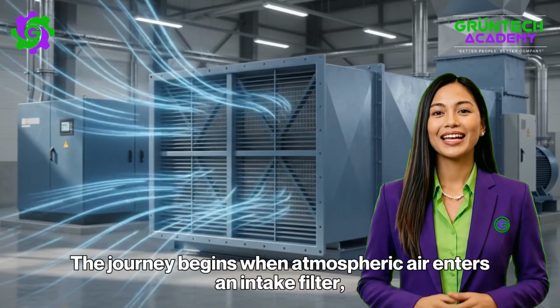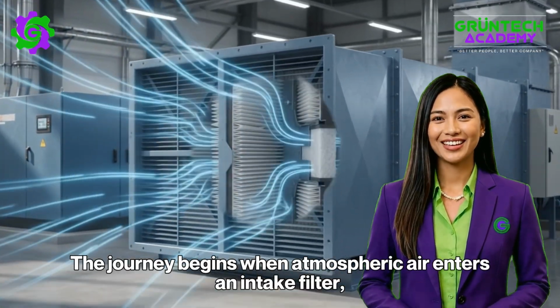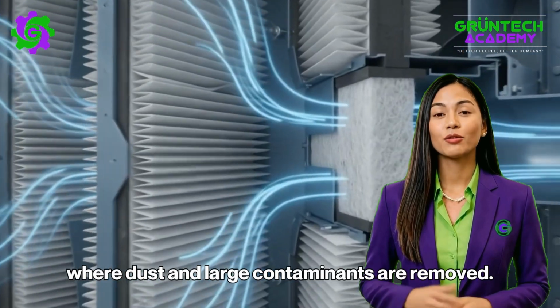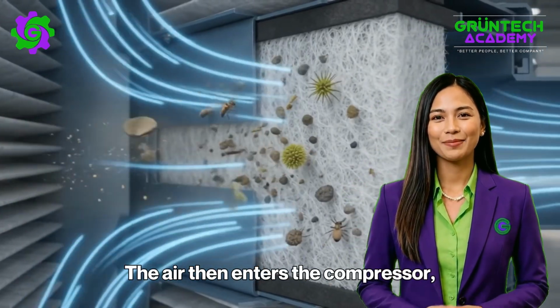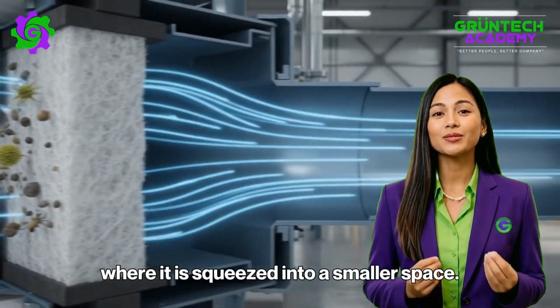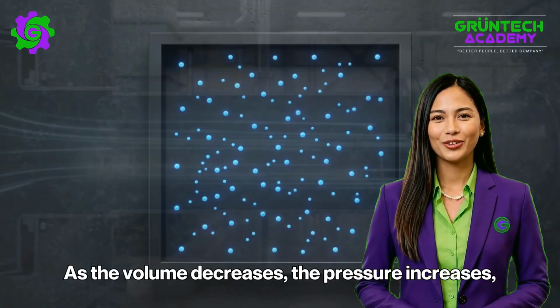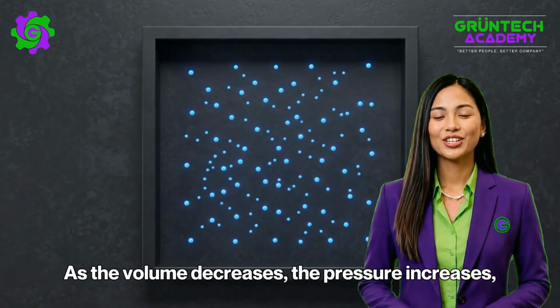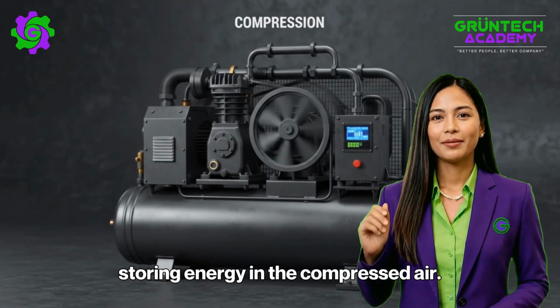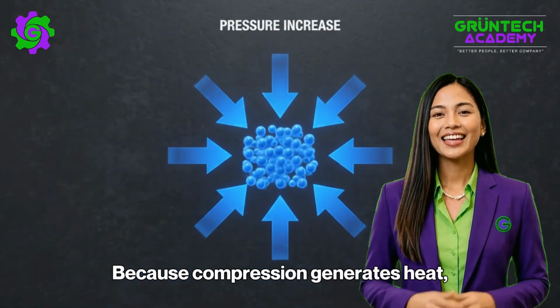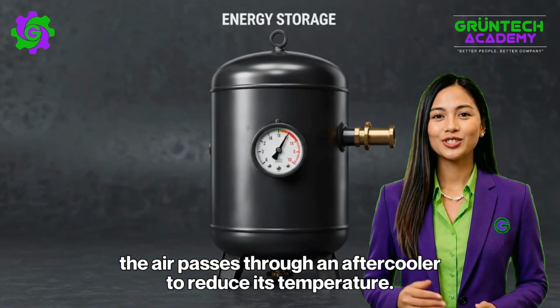The journey begins when atmospheric air enters an intake filter, where dust and large contaminants are removed. The air then enters the compressor, where it is squeezed into a smaller space. As the volume decreases, the pressure increases, storing energy in the compressed air. Because compression generates heat, the air passes through an aftercooler to reduce its temperature.